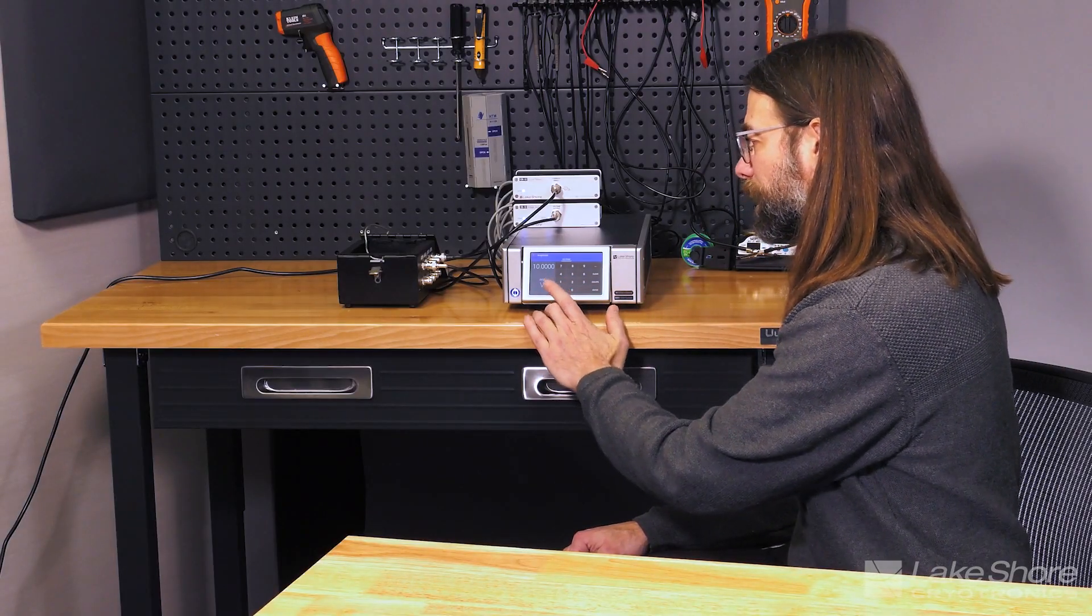But now what I'd like to show you is again 994. If we switch back over and we change the polarity so now instead of sourcing a positive 10 volts we're just going to switch that to a negative 10 volts. Now we would expect that our resistance would be the same value but you see it actually has dropped down to 991 megaohms.